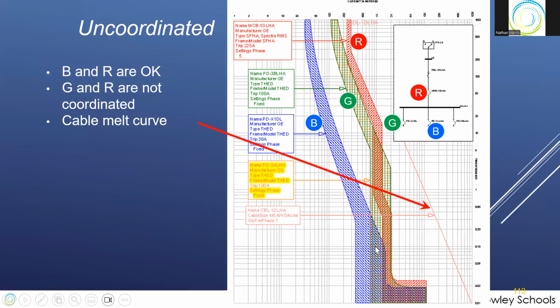Here's an example of one that's uncoordinated. So R, G, B are the three mains and two feeders. Here's cable melt out here, this red line, and B and R are okay. Blue and the red are okay. The green and the red are not coordinated right in here. And so it's highlighted, saying, hey, we've got to change these settings.